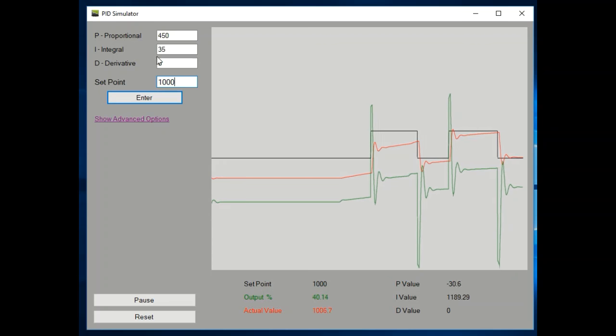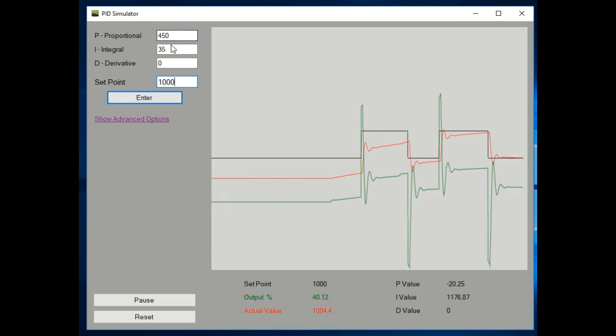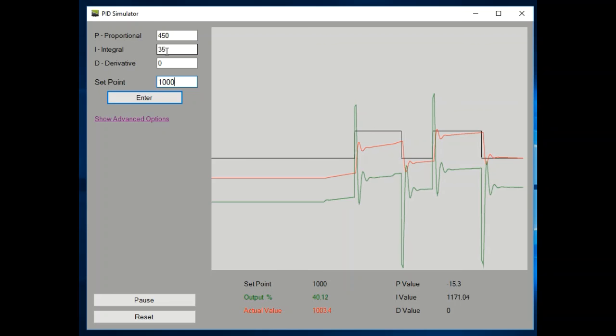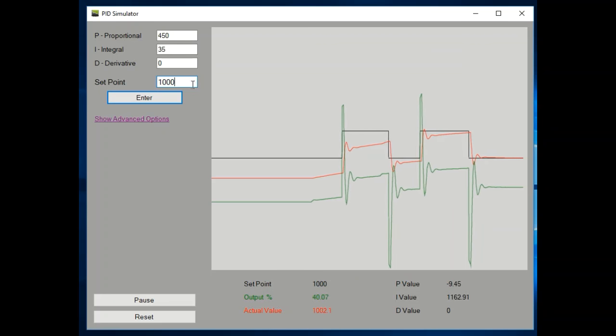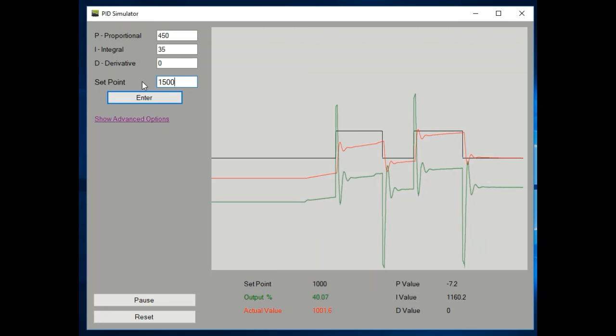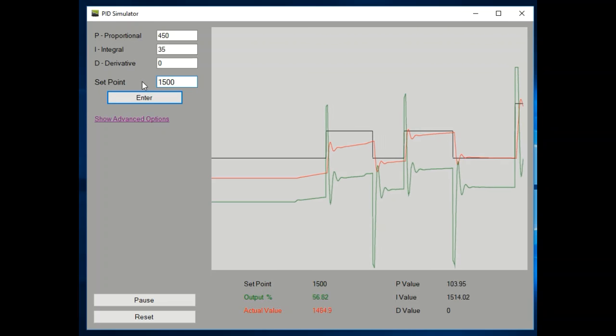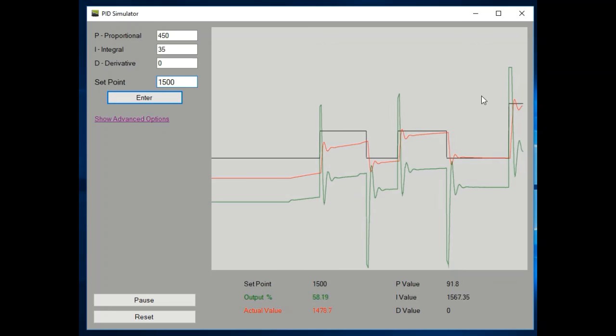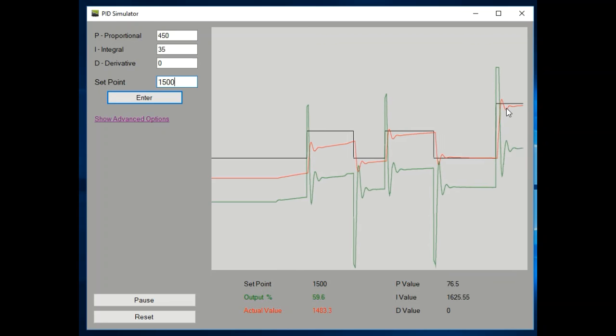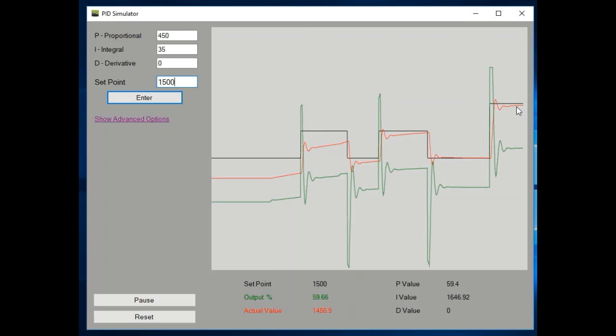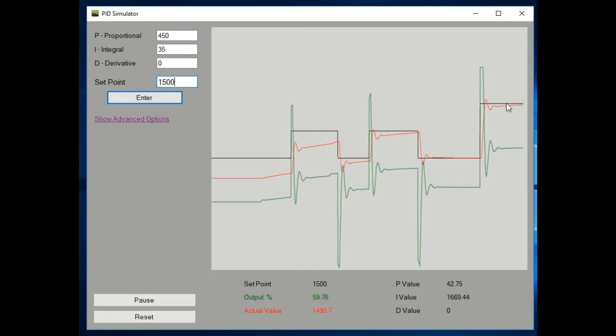A lot of controllers will work with just a P and an I and not a D value. So you can tune the proportional, then tune the integral, and have a controller that works for you. This reaction time is better, but I want to see what it does with a larger set point change. With a large set point change, we have a little bit of overshoot from the proportional, but then with the integral it's not actually accumulating as fast as I like and keeps us a little below the set point.